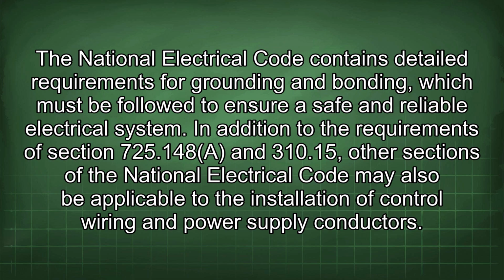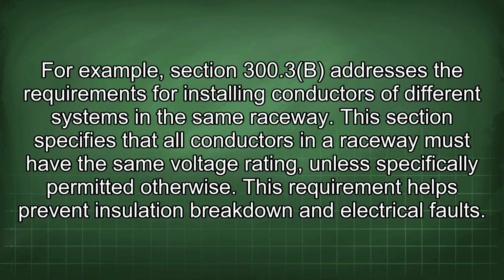reliable electrical system. In addition to the requirements of Section 725.148 and 310.15, other sections of the National Electrical Code may also be applicable to the installation of control wiring and power supply conductors. For example, Section 300.3(B) addresses the requirements for installing conductors of different systems in the same raceway. This section specifies that all conductors in a raceway must have the same voltage rating unless specifically permitted otherwise. This requirement helps prevent insulation breakdown and electrical faults.